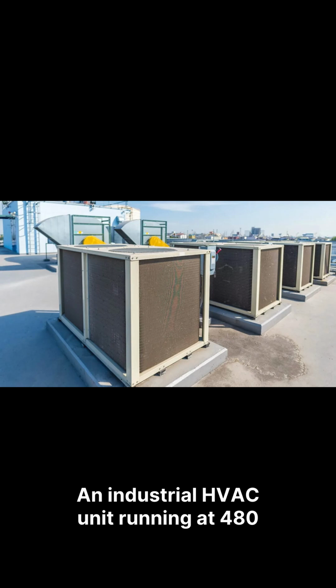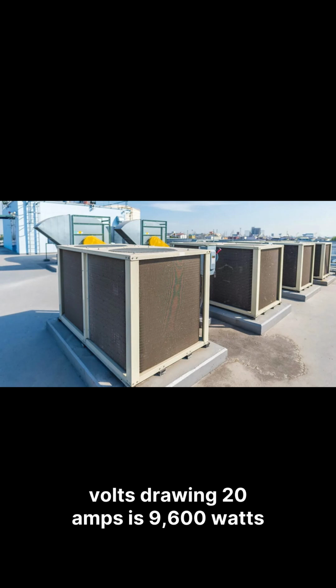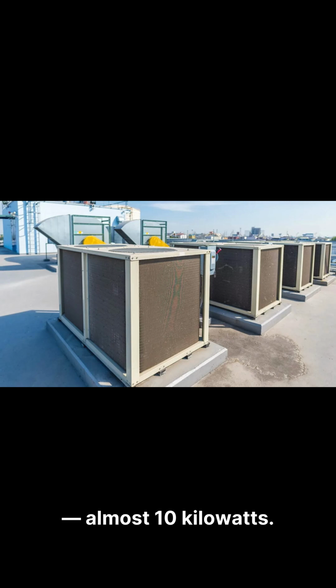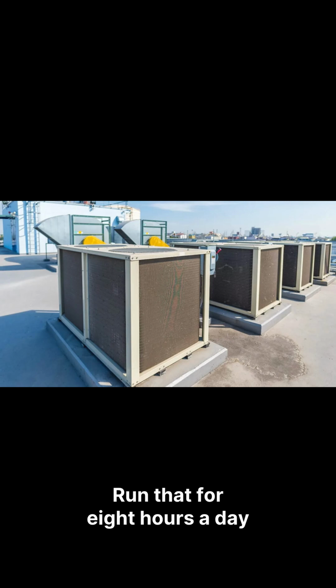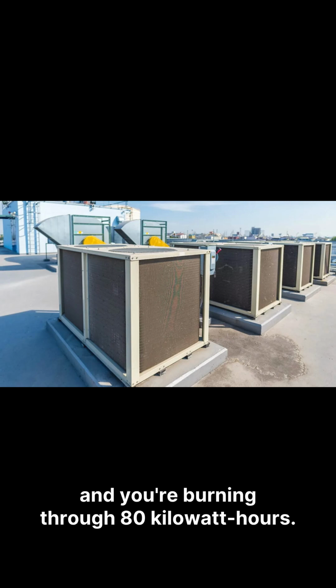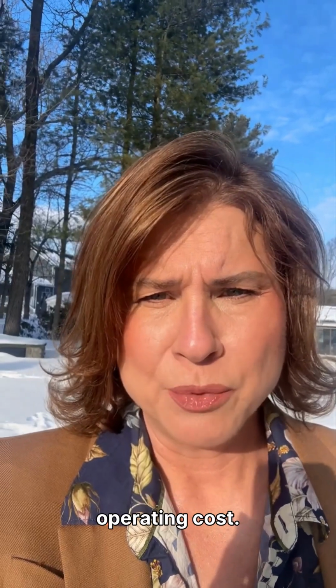Simple. Now scale that up. An industrial HVAC unit running at 480 volts drawing 20 amps is 9,600 watts, almost 10 kilowatts. Run that for 8 hours a day and you're burning through 80 kilowatt hours. That's a line item on the owner's operating cost.